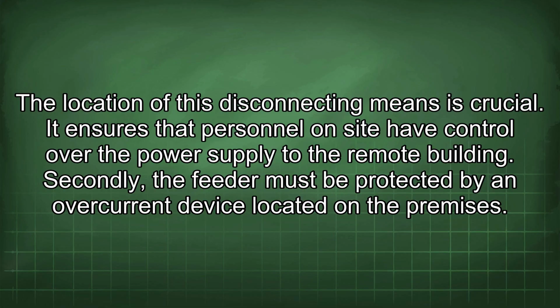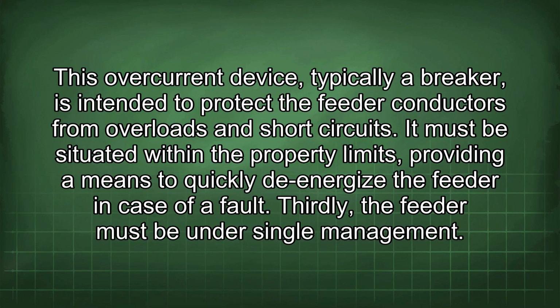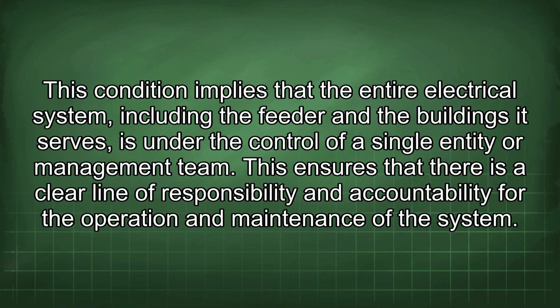Secondly, the feeder must be protected by an overcurrent device located on the premises. This overcurrent device, typically a breaker, is intended to protect the feeder conductors from overloads and short circuits. It must be situated within the property limits, providing a means to quickly de-energize the feeder in case of a fault. Thirdly, the feeder must be under single management. This condition implies that the entire electrical system, including the feeder and the buildings it serves, is under the control of a single entity or management team. This ensures that there is a clear line of responsibility and accountability for the operation and maintenance of the system.